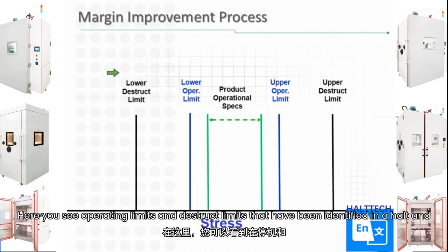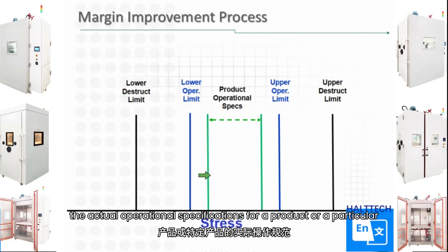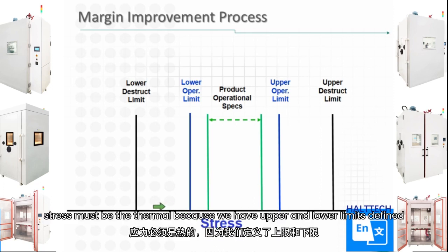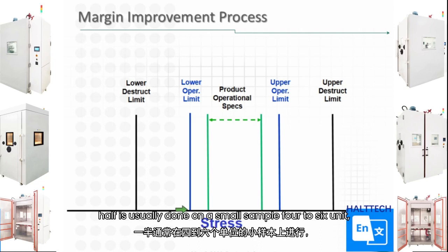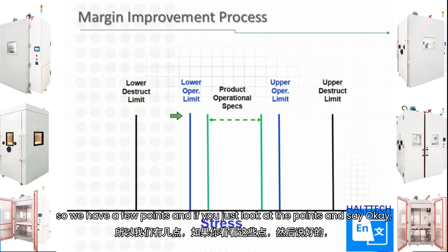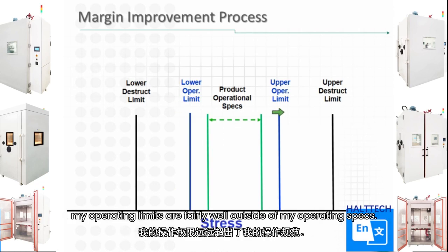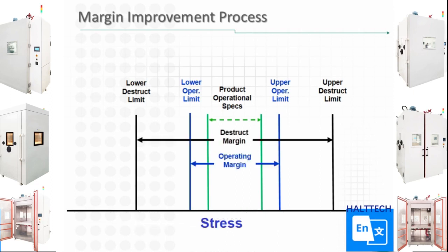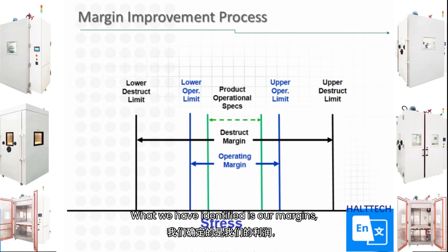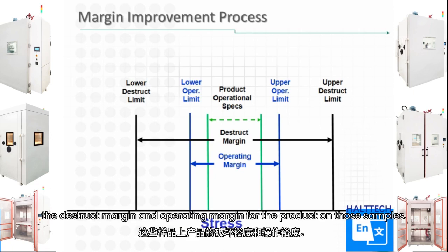Here you see operating limits and destruct limits identified in a HALT, and the actual operational specifications for a product for a particular stress—must be thermal, since we have upper and lower limits defined. HALT is usually done on a small sample, 4 to 6 units, so we have just a few points. If you look at the points and say your operating limits are fairly well outside your operating specs, what we've identified is our margins—the destruct margin and operating margin—for the product on those samples.